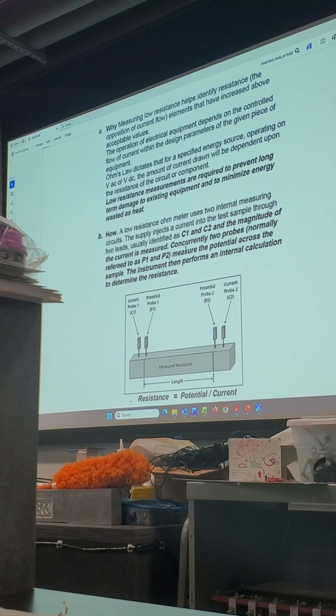So B, how do we do it? We took a look at the circuit diagram. Here's another helpful representation. A low resistance ohmmeter uses two internal measuring circuits, and we already know what those are by now. A supply injects a current into the test sample through two leads, usually identified as C1 and C2, and the magnitude of the current is measured. Concurrently, two probes, normally referred to as P1 and P2, measure the potential across the sample. The instrument then performs an internal calculation, as we saw, to determine the resistance.